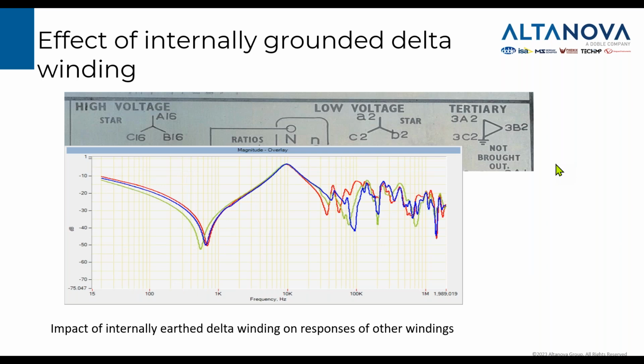Here is another example of additional winding which can play a role. This was a small transformer connected star delta, but the delta was buried inside the transformer and grounded in one point, and it was not brought to the tank. So at first view, you wouldn't see the terminals of that tertiary winding, and you wouldn't even know it is there until you looked at the rating plate.